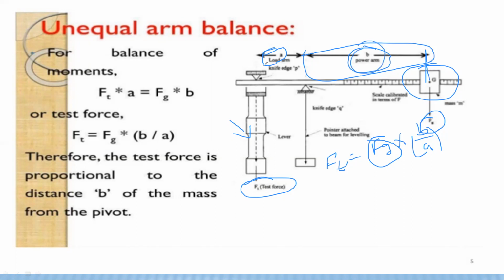much smaller standard weights, the poise weight WP and the pan weight WS. A proper combination of the pan weight and the adjustment of the poise weight lever arm along the calibrated scale is ensured to bring the beam to null or balanced position. To simplify this analysis, assume that the poise weight lies at the zero beam position and that the weights W1 and W2 are placed at the positions shown.